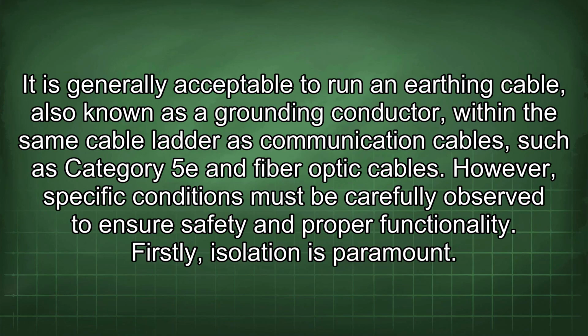It is generally acceptable to run an earthing cable, also known as a grounding conductor, within the same cable ladder as communication cables such as Category 5E and fiber optic cables. However, specific conditions must be carefully observed to ensure safety and proper functionality.